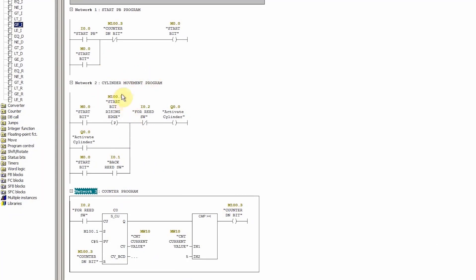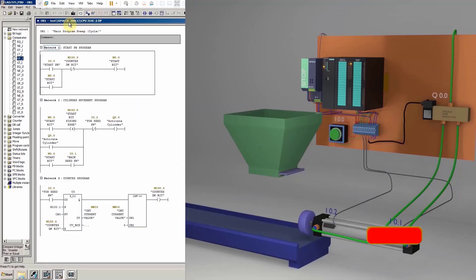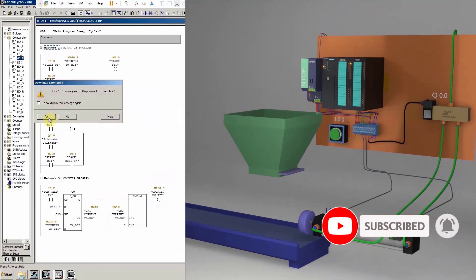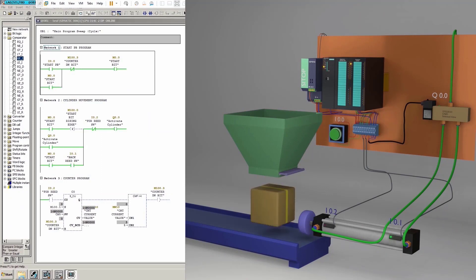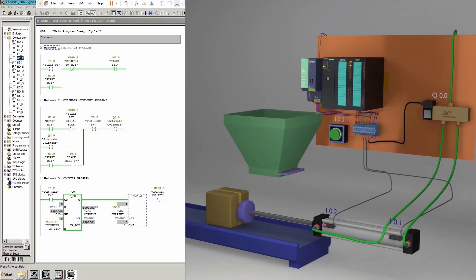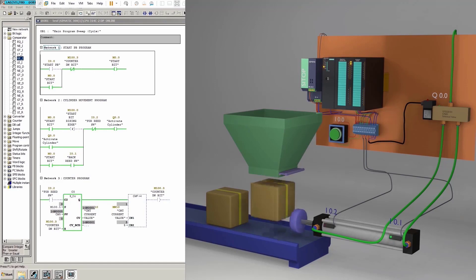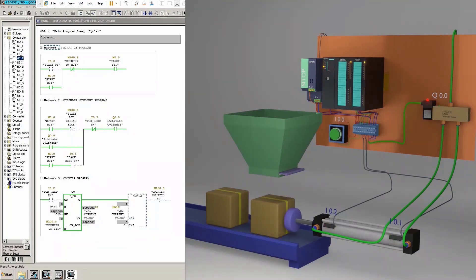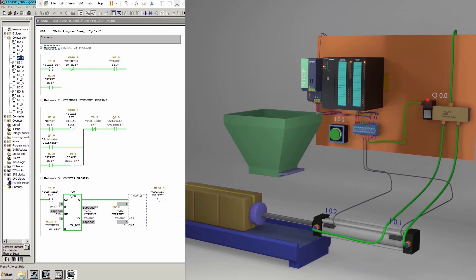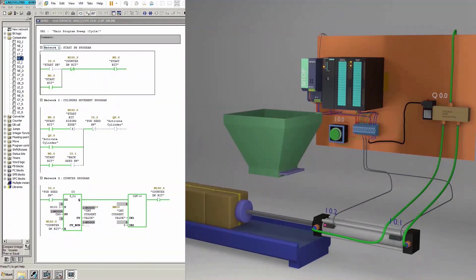Now we upload this logic into the PLC and monitor the ladder logic. As soon as we press the start push button I0.0, on the rising edge of start bit M0.0 the solenoid valve Q0.0 turns on and the cylinder moves forward. When forward reed switch I0.2 turns on, the solenoid valve turns off and the cylinder moves backward. When back reed switch I0.1 detects the piston, Q0.0 turns on again. Each time the cylinder reaches the forward position the counter increments by one, and when it reaches 5 the start bit resets and the counter resets to zero.